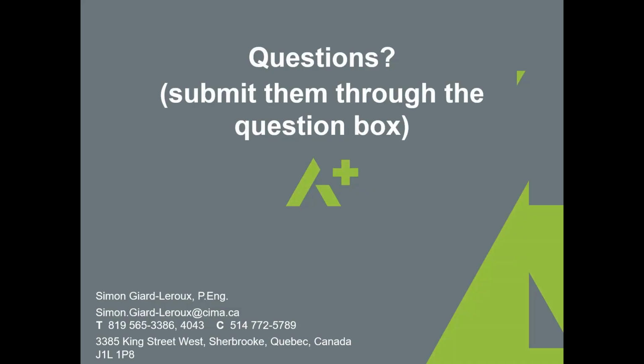Okay. Next question: how will tables in 70E be affected by the new calculation method, particularly for troubleshooting equipment under 600 volts? The 70E table will be updated in the next version to consider this. Basically, you had a column that said the maneuver, and you had a table that said the PPE requirements. These will be updated in the new NFPA 70E.